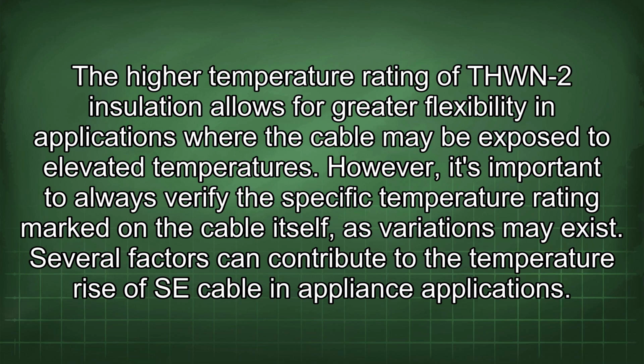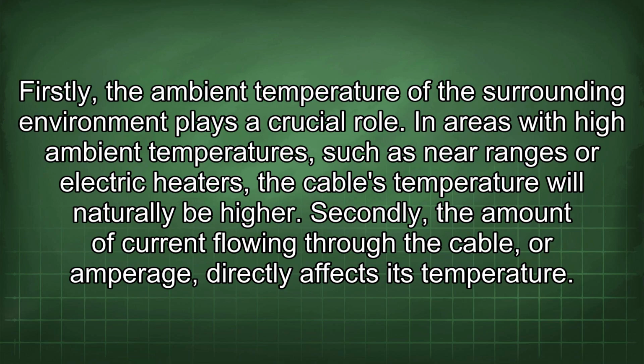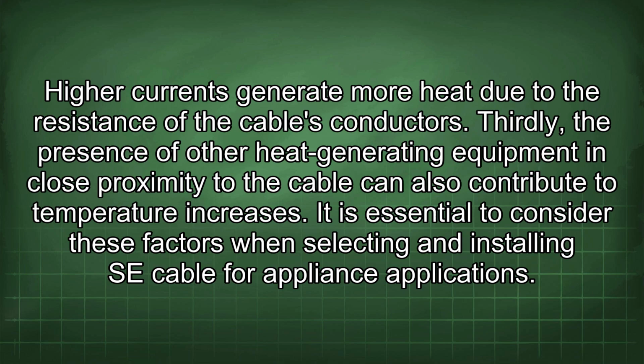exist. Several factors can contribute to the temperature rise of SE cable in appliance applications. Firstly, the ambient temperature of the surrounding environment plays a crucial role. In areas with high ambient temperatures, such as near ranges or electric heaters, the cable's temperature will naturally be higher. Secondly, the amount of current flowing through the cable, or amperage, directly affects its temperature. Higher currents generate more heat due to the resistance of the cable's conductors. Thirdly, the presence of other heat-generating equipment in close proximity to the cable can also contribute to temperature increases. It is essential to consider these factors when selecting and installing SE cable for appliance applications.